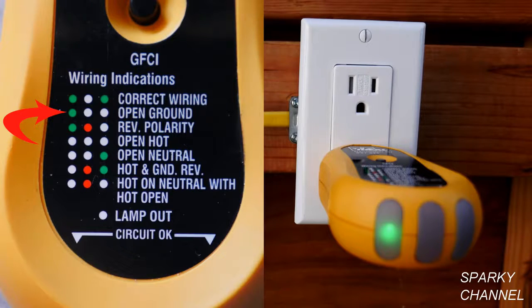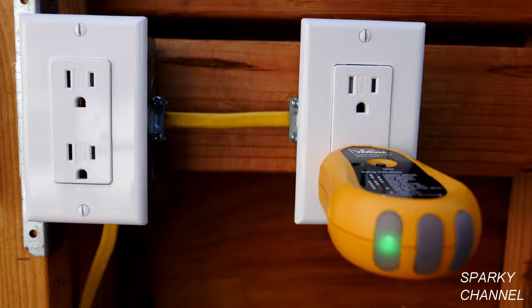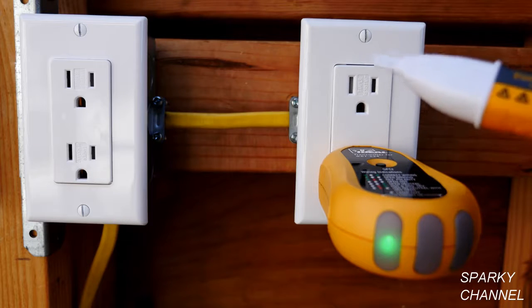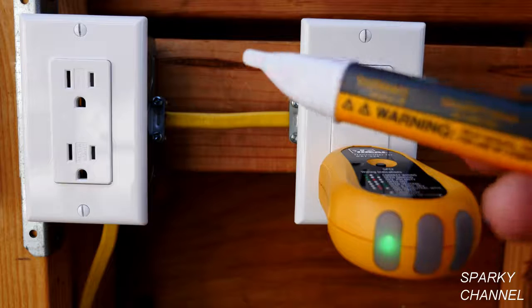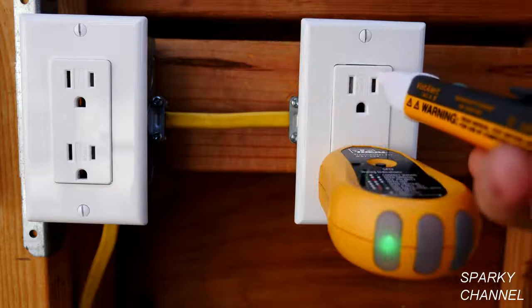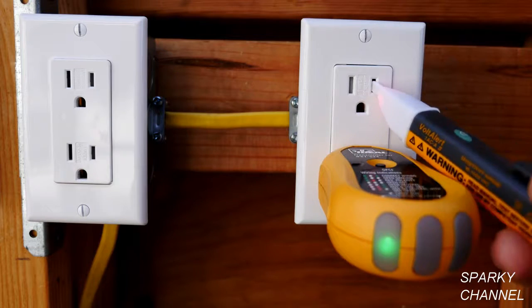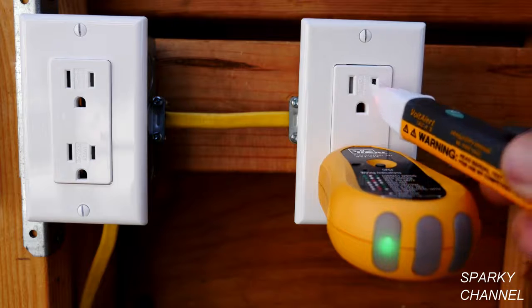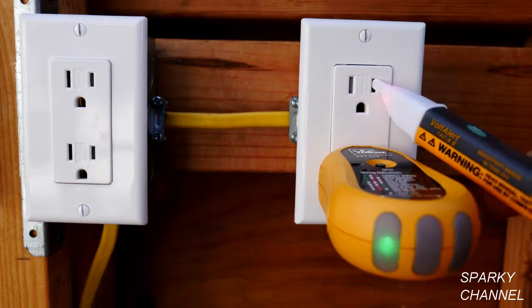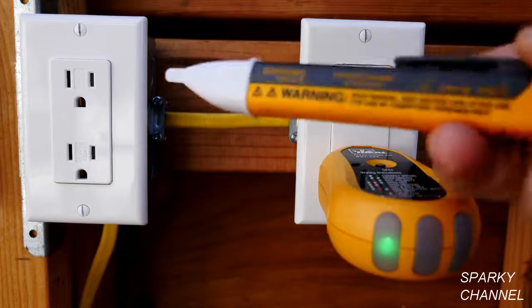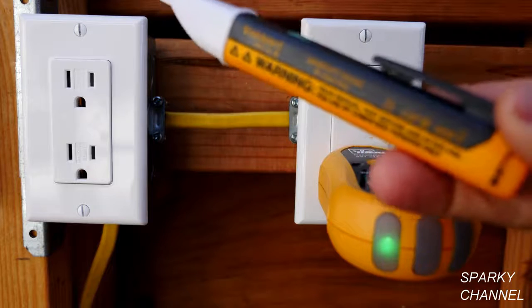It's always much better to have grounded receptacles because this will protect people from dangerous events like lightning strikes and power surges. Once we've determined that it's an open ground, the first thing we need to do is test our voltage detector. I'll put it into the hot slot and you see it lights up and has an audible beep. So we see that the voltage tester is working properly.